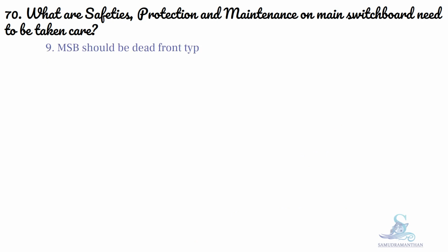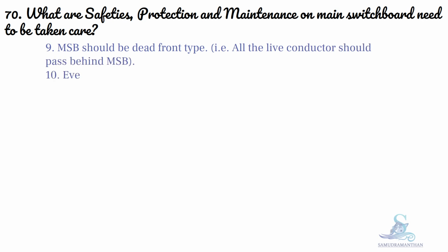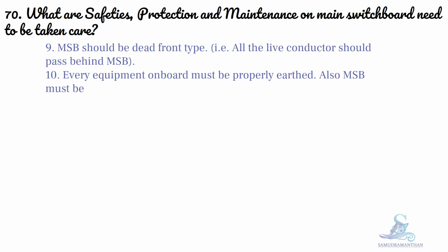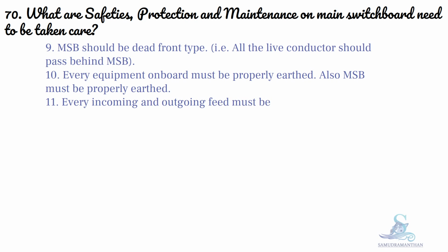MSB should be dead front type, that is, all the live conductors should pass behind the MSB. Every equipment on board must be properly earthed. Also, the MSB must be properly earthed. Every incoming and outgoing feed must be protected by a switch, fuse or circuit breaker.